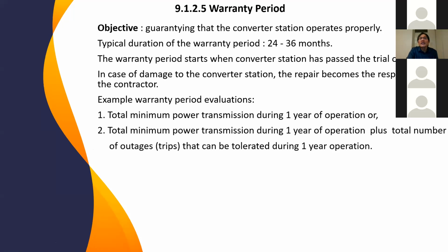The objective here is to guarantee the converter station operates properly. The typical duration of the warranty period is between 2 and 3 years. Some depend on the customer. Sometimes the customer asks for, let's say, 7 years, depending. This is only typical. For example, for warranty period evaluation, how to evaluate: either the evaluation measures the minimum power transmission during 1 year of operation, plus the total number of outages that can be tolerated during 1 year of operation. Let's say if the requirement is only 5 outages, but we have 6, by this in year 1, we fail to meet the warranty period requirement.